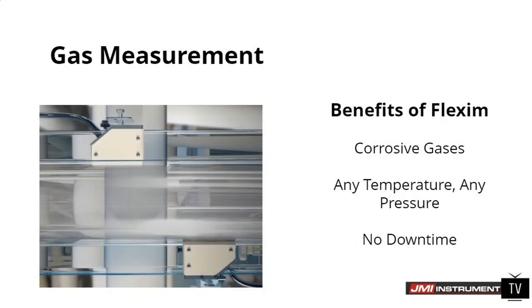So the benefits of Flexim: it's basically the benefits of a clamp-on flow meter for liquid or gas. We're outside the pipe. So what that means is corrosive gases don't bother us because we're outside the pipe. Temperature or pressure: obviously, the pressure can be as high as it wants to be, but we do have those minimums for the metal pipe. Temperature, typically in the past, we run up to about 130 degrees Fahrenheit with the standard material. If we go higher than that, we have some dampening that we can paint on the pipe that's high temperature, up to about 1200 degrees. And then we have transducers that'll go right up to around 320 degrees.